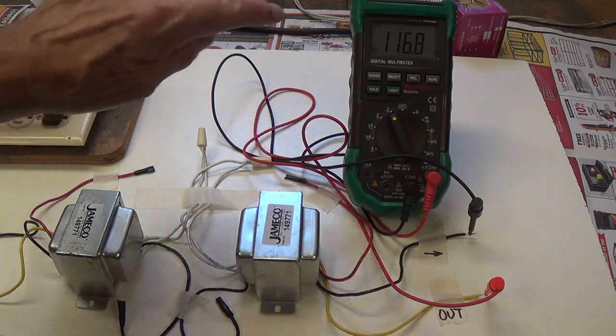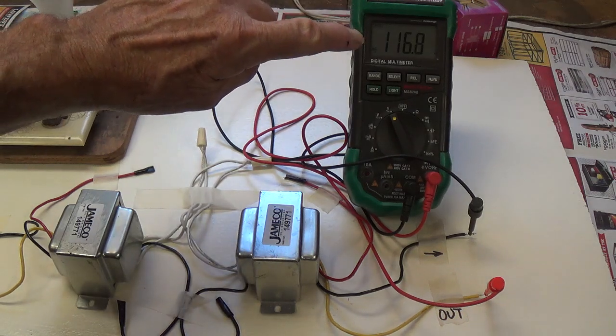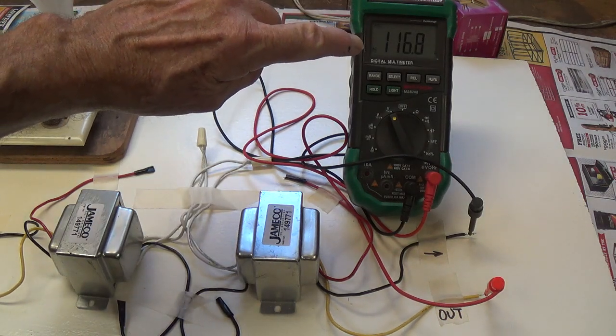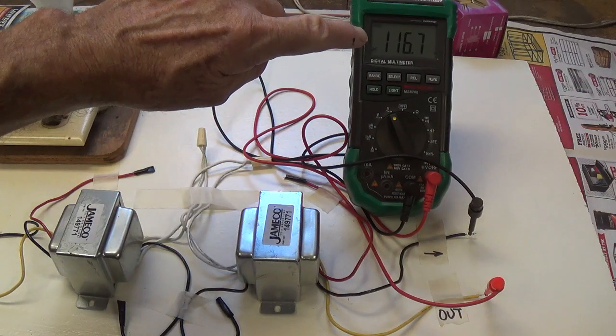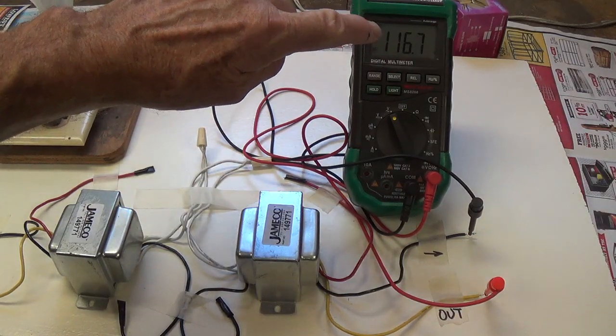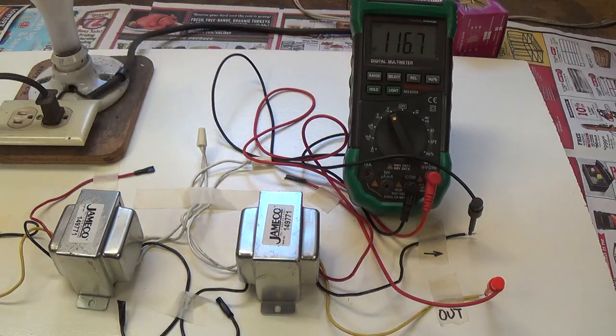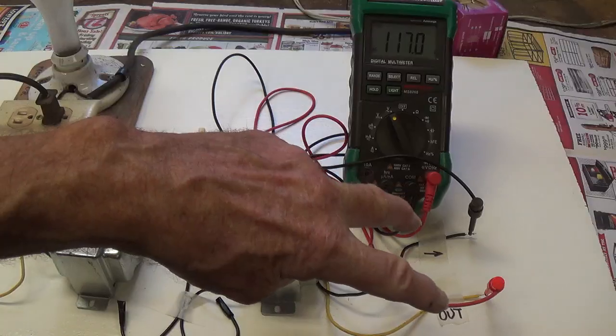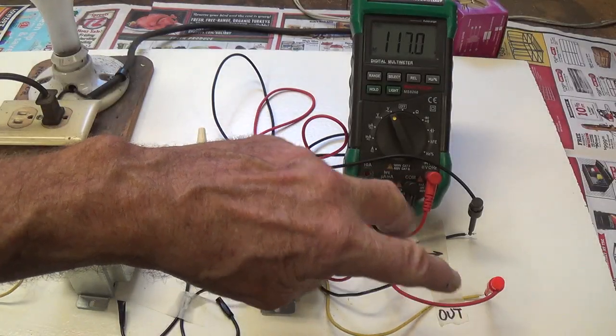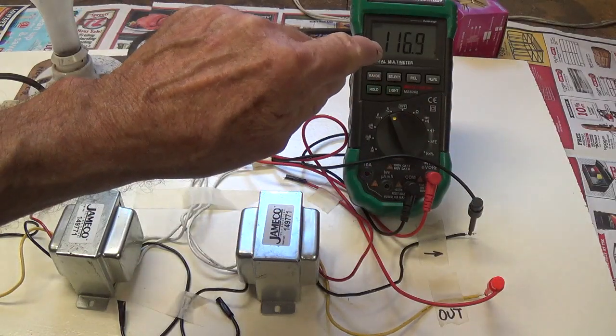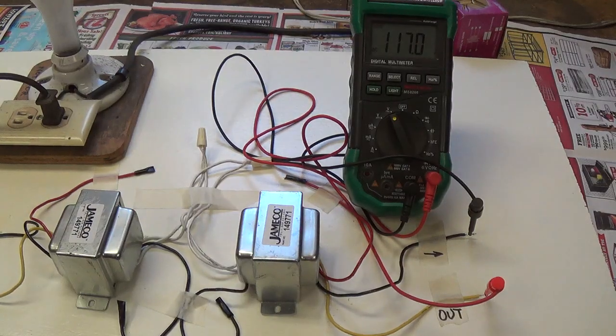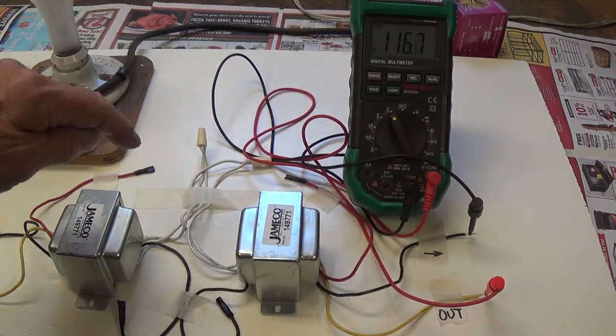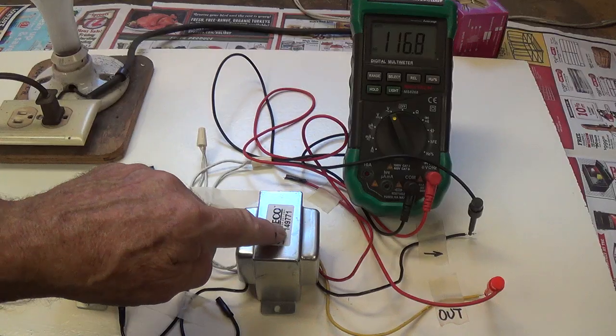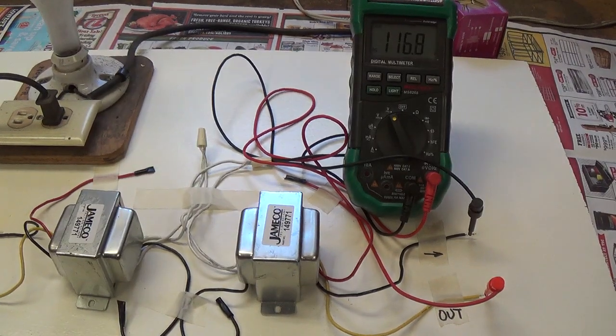Well, actually not too bad. 116.7 or 0.8, which is still higher than the 115 volts that we used to get from the receptacle. Now granted, that is no load voltage. Once we start running current through this, the voltage level will probably go down. But for now, I'm pretty happy that the voltage drop across the 2 transformers is not all that great.